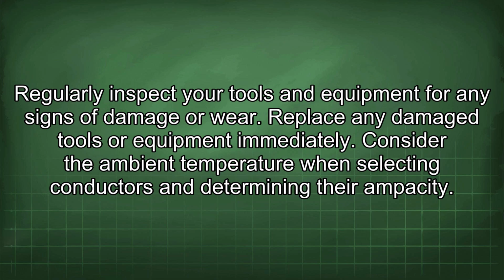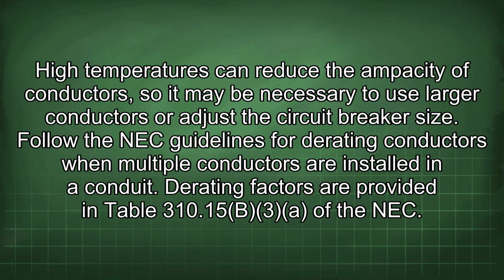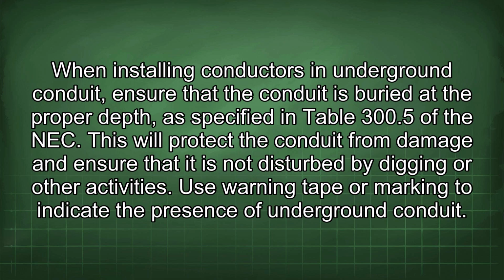Consider the ambient temperature when selecting conductors and determining their ampacity. High temperatures can reduce the ampacity of conductors, so it may be necessary to use larger conductors or adjust the circuit breaker size. Follow the NEC guidelines for derating conductors when multiple conductors are installed in a conduit. Derating factors are provided in Table 310.15(B)(3) of the NEC. When installing conductors in underground conduit, ensure that the conduit is buried at the proper depth, as specified in Table 300.5 of the NEC.